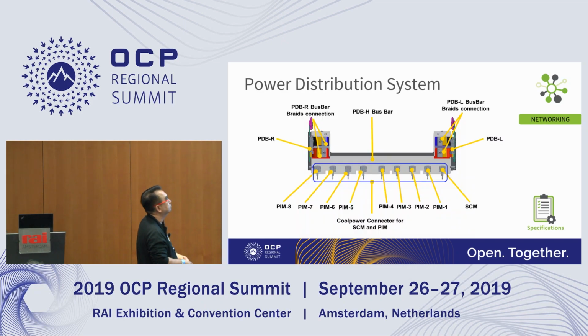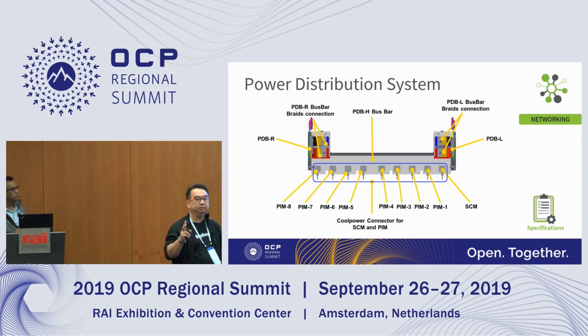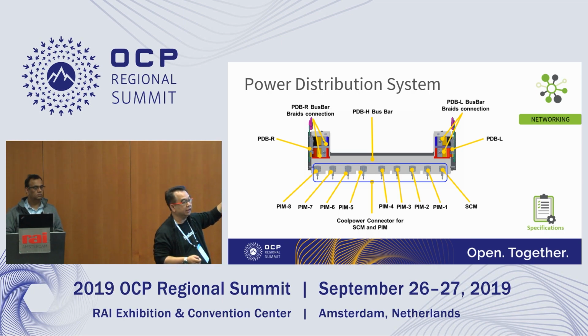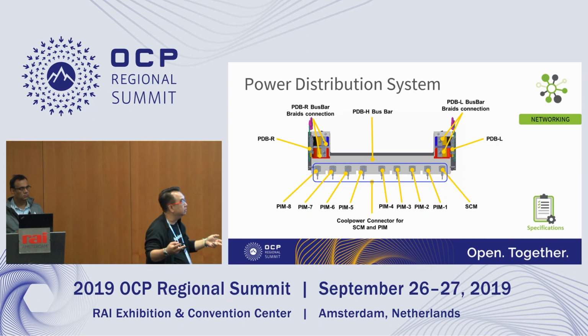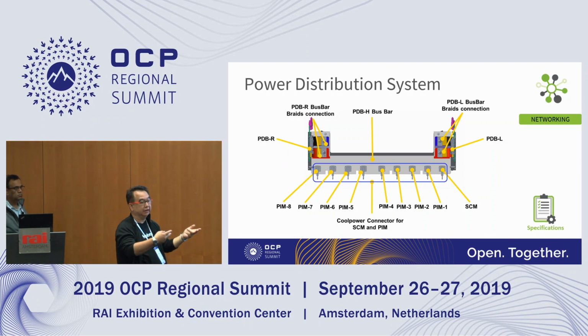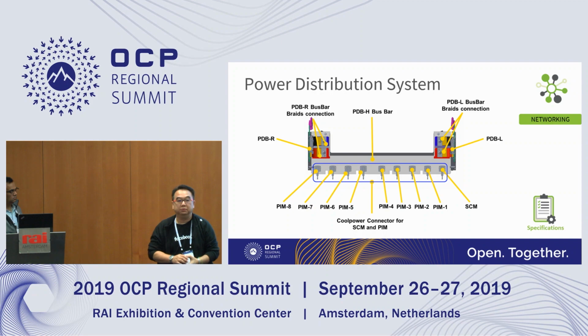Next, we flip the distribution system to show how it's connected from the PSU to the PIM card, how the power is being distributed. The PDB connects to the 4 PSUs on the rear side of the system, and we utilize busbar braided connections, 2 copper braided cables on each side for ground and power, to connect to the busbar at different layers. It then connects through the Coolpower connectors and distributes power to each of the front modules.